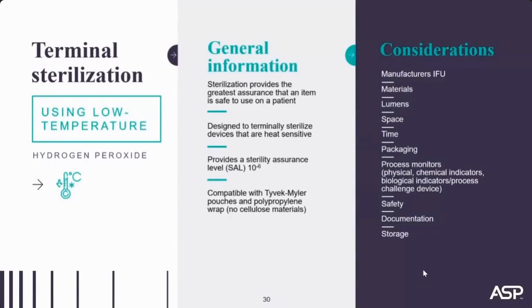Terminal sterilization provides a packaged product that can go on the shelf for later use, or you can use it immediately. Terminal sterilization provides a sterility assurance of 10 to the minus 6, meaning that there's a chance in a million that a microorganism has survived.